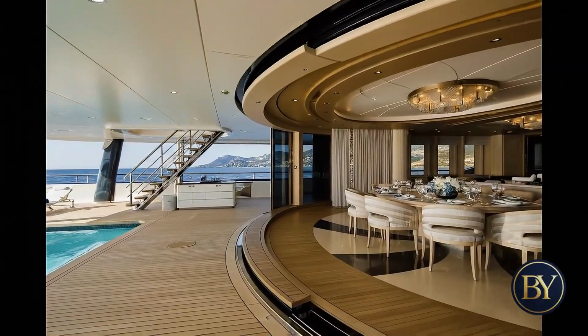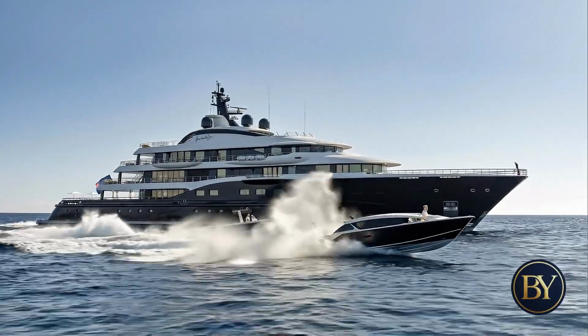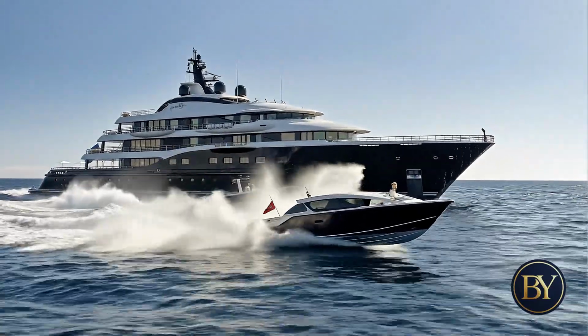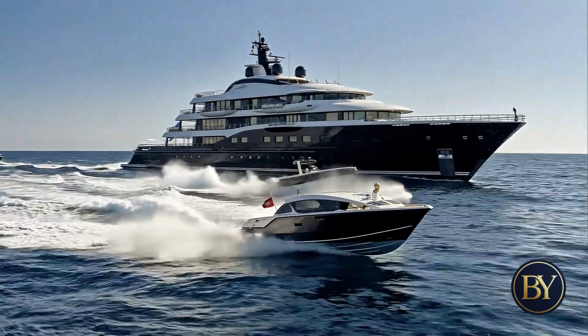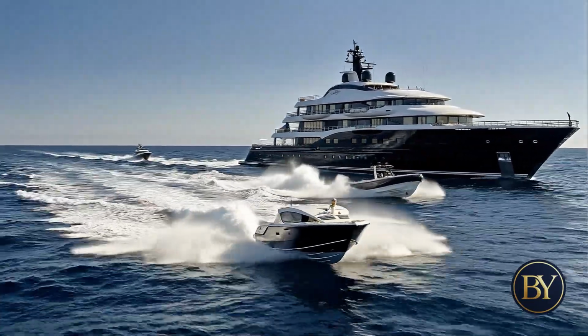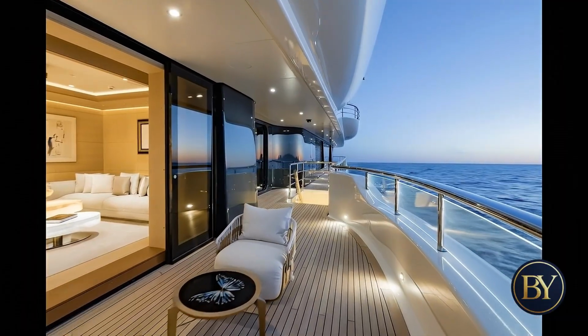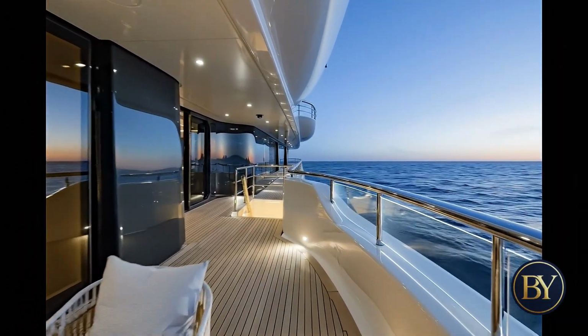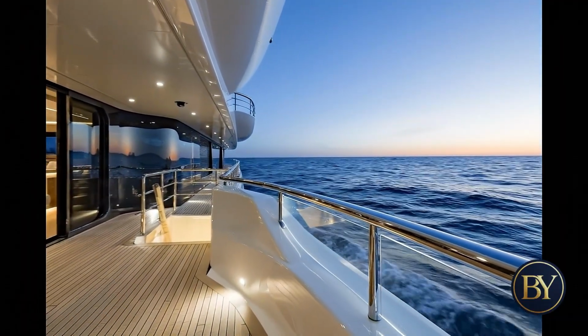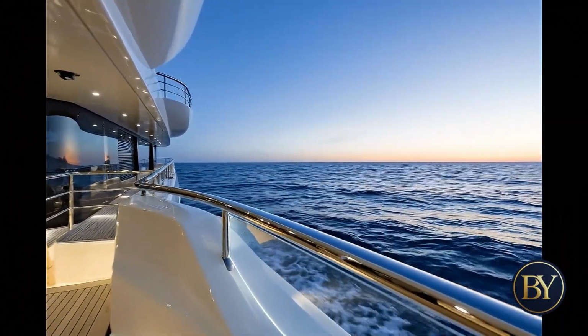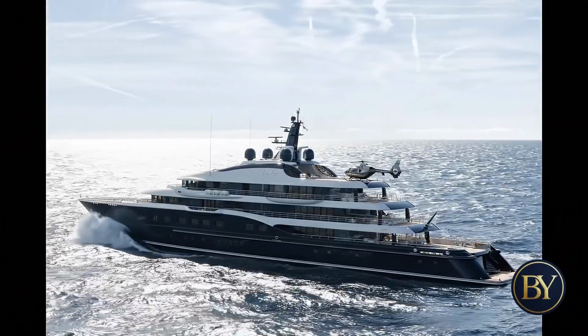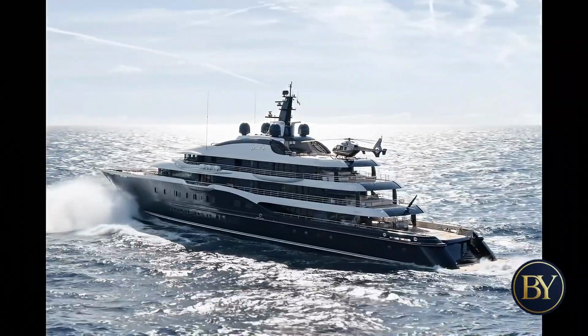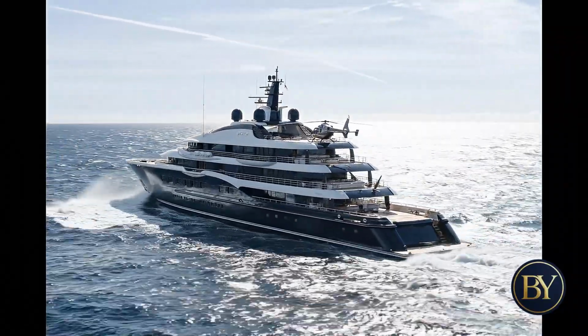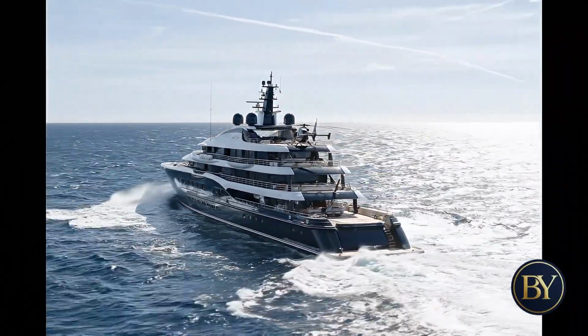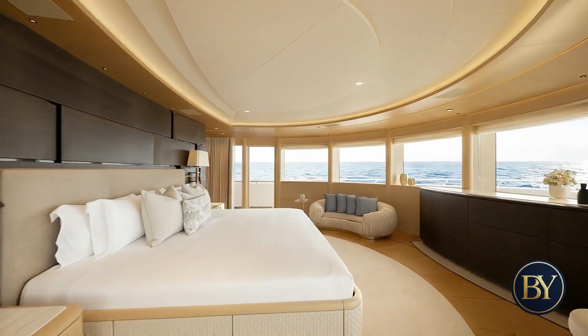So how does the peak shaving mode actually fix this problem? The massive lithium battery bank acts as an instantaneous buffer. When that massive power spike hits from the ovens and the AC, the batteries instantly dump power into the grid to flatten the demand curve. The generator doesn't even feel the spike. It just keeps happily running at its perfectly efficient 50% sweet spot. And then later, when the demand drops back down, the generator slowly recharges the batteries.